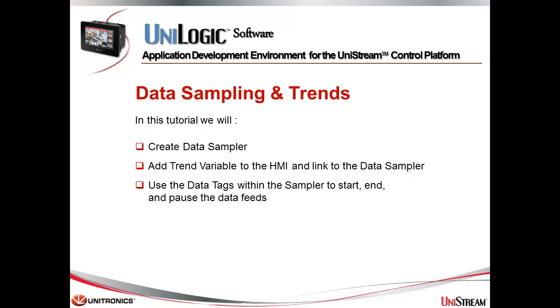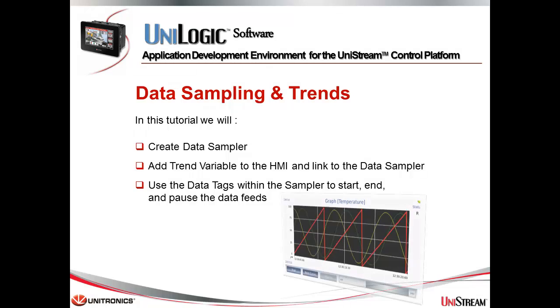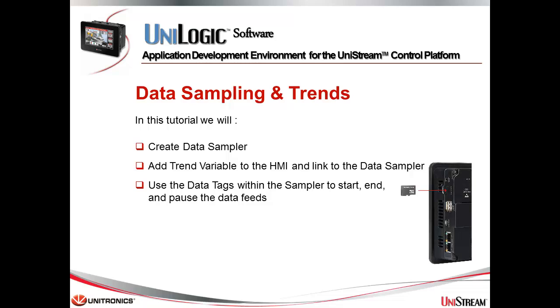The following tutorial shows you how easy it is to create and use data sampling. Using data sampling, we can log PLC tags to a file according to a predefined interval and then make use of it as a trend on the HMI, as a CSV file, and more. It is important to know that the data sampling is saved on a microSD card, which needs to be inserted in advance to the UniStream panel in its slot.